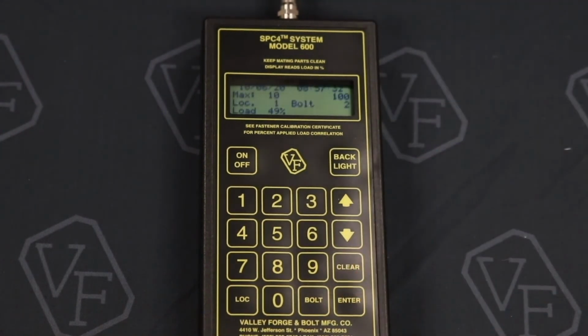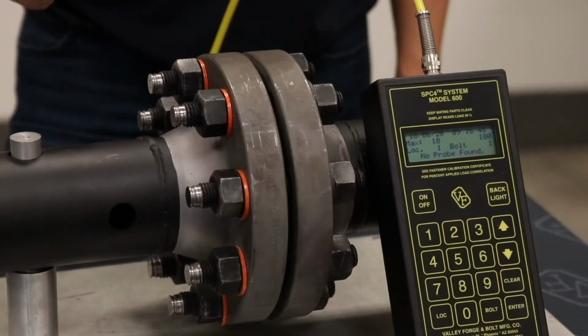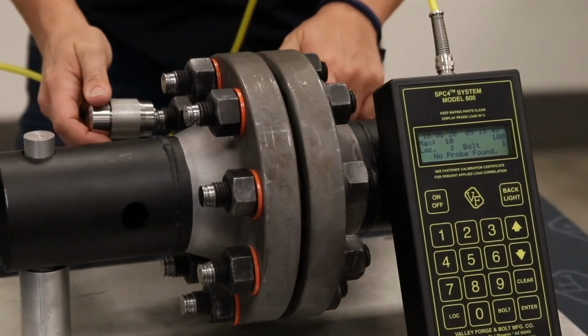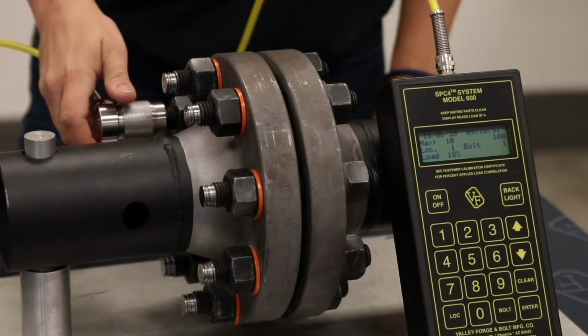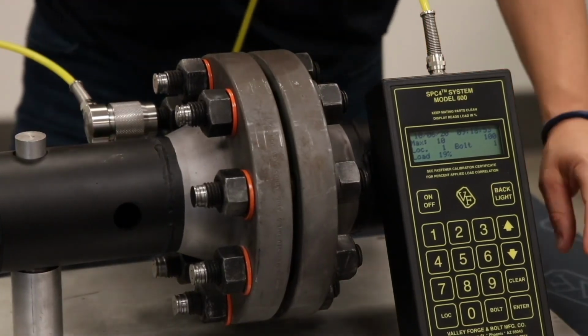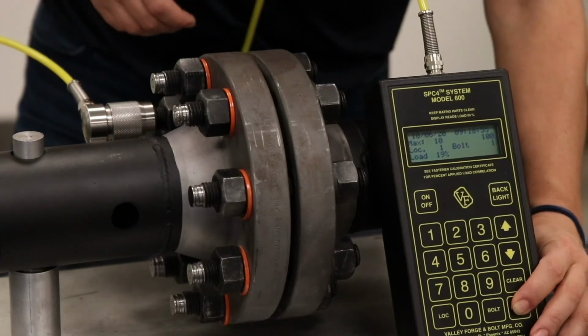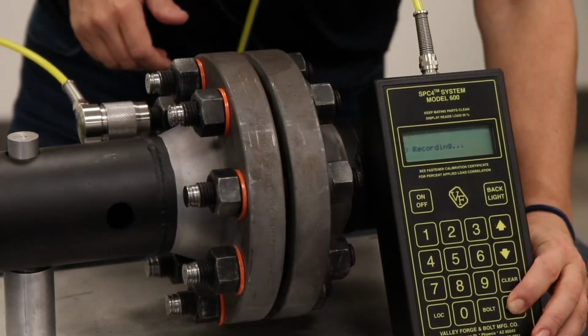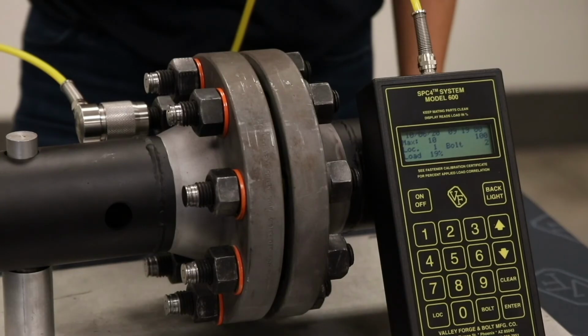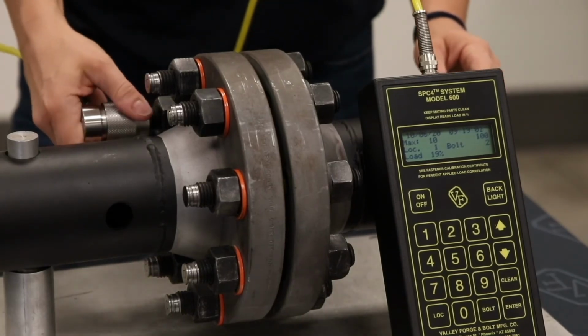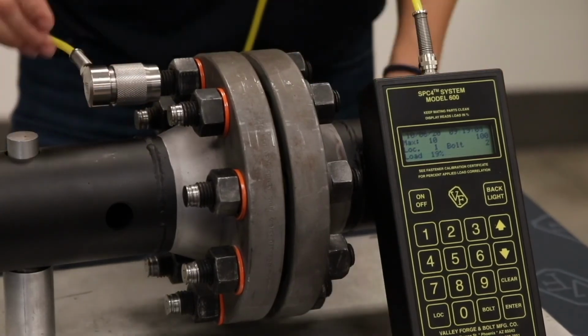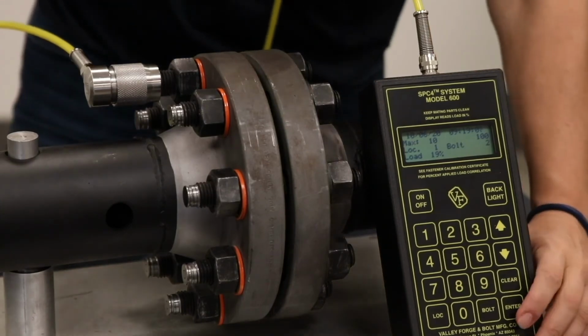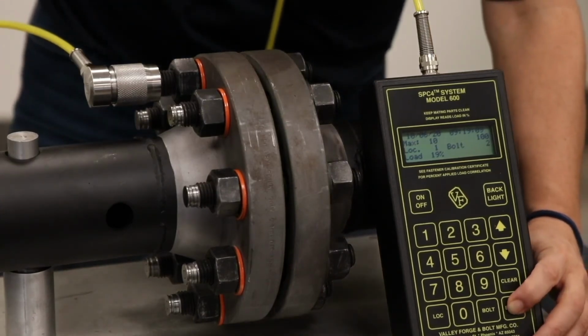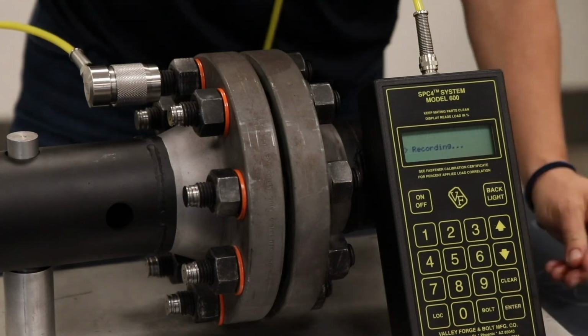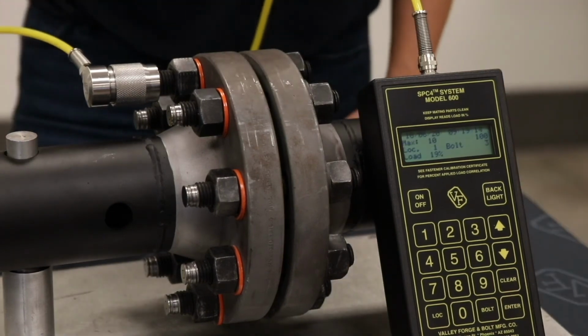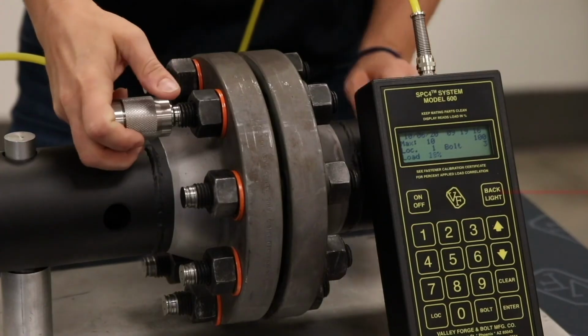Once the desired location and bolt has been set, snap the 600A probe onto the SPC4 fastener of interest. Take a data sample by pressing and holding the Enter button for a few seconds until the LCD shows recording. This will take a data sample in the set location and set bolt number. After a reading has been taken, the bolt number will automatically be incremented by 1. If at any time the environment lacks sufficient light to see the LCD, the backlight can be turned on momentarily by pressing and holding down the backlight button.